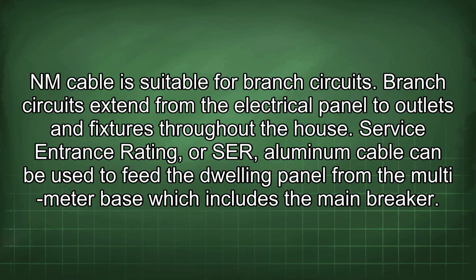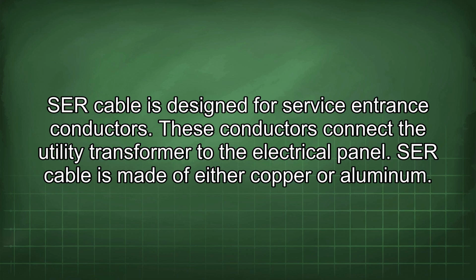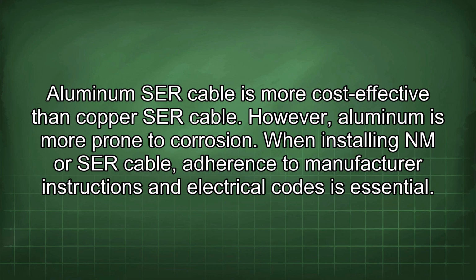Service entrance rating, or SER, aluminum cable can be used to feed the dwelling panel from the multimeter base, which includes the main breaker. SER cable is designed for service entrance conductors. These conductors connect the utility transformer to the electrical panel. SER cable is made of either copper or aluminum. Aluminum SER cable is more cost-effective than copper SER cable. However, aluminum is more prone to corrosion.